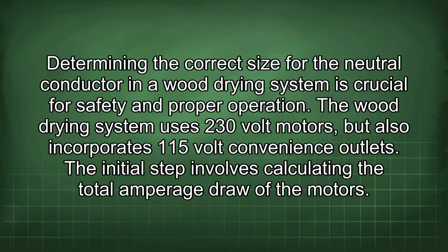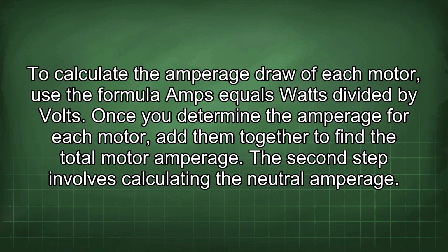Determining the correct size for the neutral conductor in a wood drying system is crucial for safety and proper operation. The wood drying system uses 230-volt motors, but also incorporates 115-volt convenience outlets. The initial step involves calculating the total amperage draw of the motors. To calculate the amperage draw of each motor, use the formula amps equals watts divided by volts. Once you determine the amperage for each motor, add them together to find the total motor amperage.